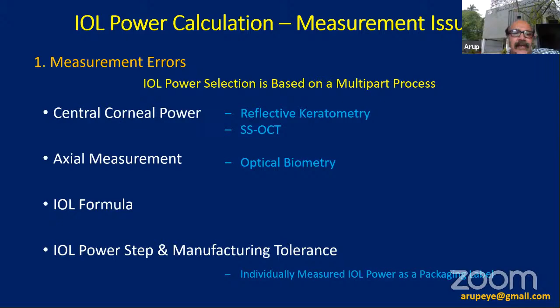And regarding measurement errors, you may take the measurements and find that your corneal curvature is very flat or very steep, or the axial length of the eye is very short or at the extremes of the range, or there is a gross difference between both eyes. This is just to give you certain important examples, and there is a whole list of validation guidelines which have to be gone through by the biometrist.